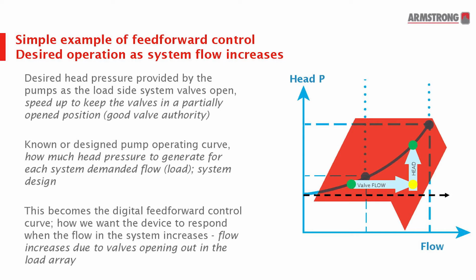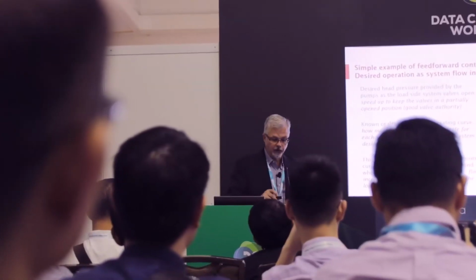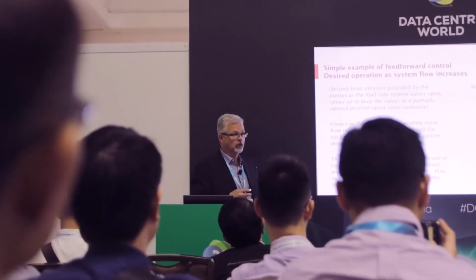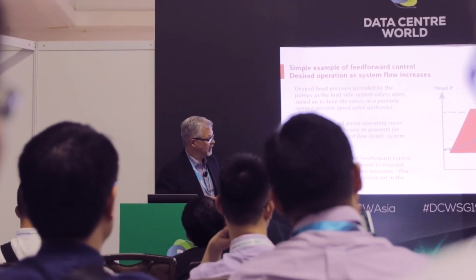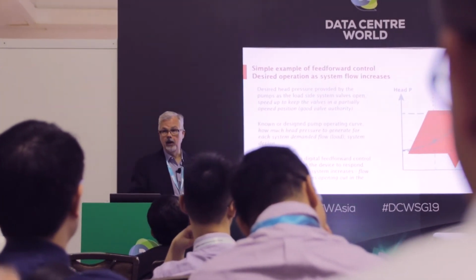So how do we do feed-forward control with a device like that? Traditionally, on a cooling coil in a system, as the load goes up, there's a requirement for more chilled water flow through that coil, and it's regulated by a valve. So valves regulate flow, and the pump generates head pressure. What we want to do as that valve opens is generate more head pressure to give that valve the best valve authority possible for that operating load. As the flow goes up, there's also more head or pressure loss in the piping system, so we need to generate more head pressure at the pump to accommodate.